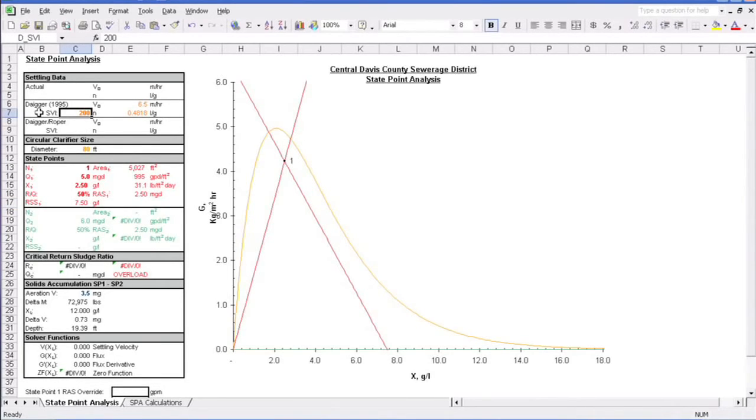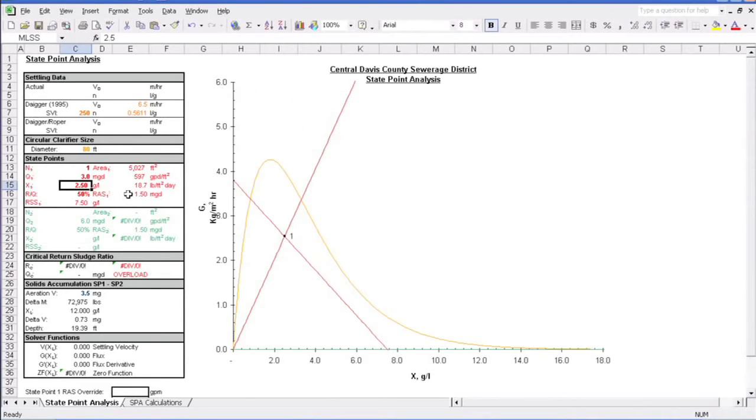Let's go back to our nice, properly functioning clarifier. The SVI is back to 250, the flow is 3MGD with a RAS running at 50% or 1.5MGD, and this time let's say that we've wasted some and our mixed liquor concentration has dropped to 2000 milligrams per liter or 2 grams per liter. We are way under the curve both in the state point and the underflow rate line. Life is good, right?